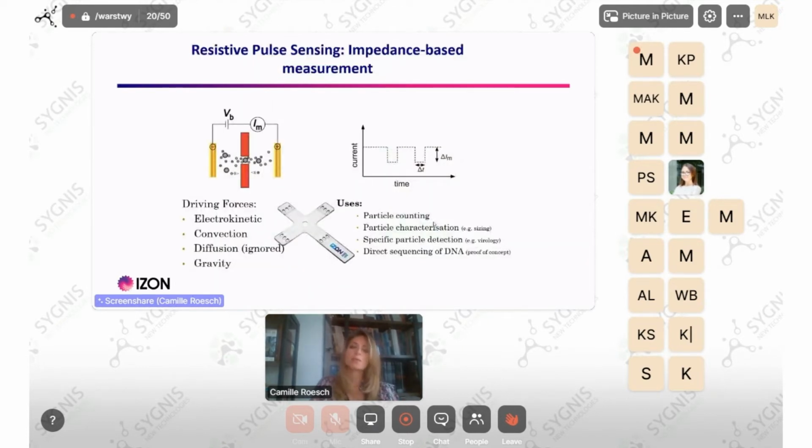So about the concept, how that works. Resistive pulse sensing is an impedance-based measurement. TRPS technology is not very new. We've just rejigged it for modern times and for analyzing smaller particles. In reality, it's a technique that derives from the Coulter counter. Maybe you're familiar with it. A Coulter counter is an instrument that used to be used for cell analysis. We've just taken that technique and rejigged it, and we were able to measure even smaller particles.